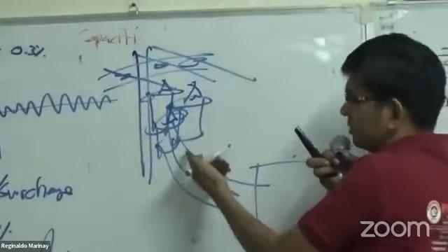The secondary - the voltage here is around 34.5 kilovolts line to line, that's a high voltage. The lower voltage side is around 250 or 240 volts - a low voltage, but it has a larger capacity wire because the voltage is lower. So your wire is thicker, but your voltage is lower - the lower the voltage, the larger the current in the transformer. That principle is carried by the motor also - if you apply a low voltage to your motor, it will draw a larger amount of current. That is the behavior of the motor, so do not allow your motor to be supplied by a lower voltage.